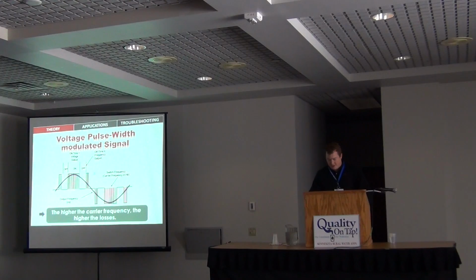So the darker line represents a typical AC sine wave, and the rectangular waves are the pulse width modulated output of the VFD. It's a DC voltage, so that's always constant, and so the voltage is always the same height. The amplitude is constant over the entire frequency range. Basically, the lower resultant voltage at the motor is done by shorter pulses. So the width of the pulse is actually used to determine the actual output voltage seen by the motor. And I'll show you another slide here in a second that describes that.